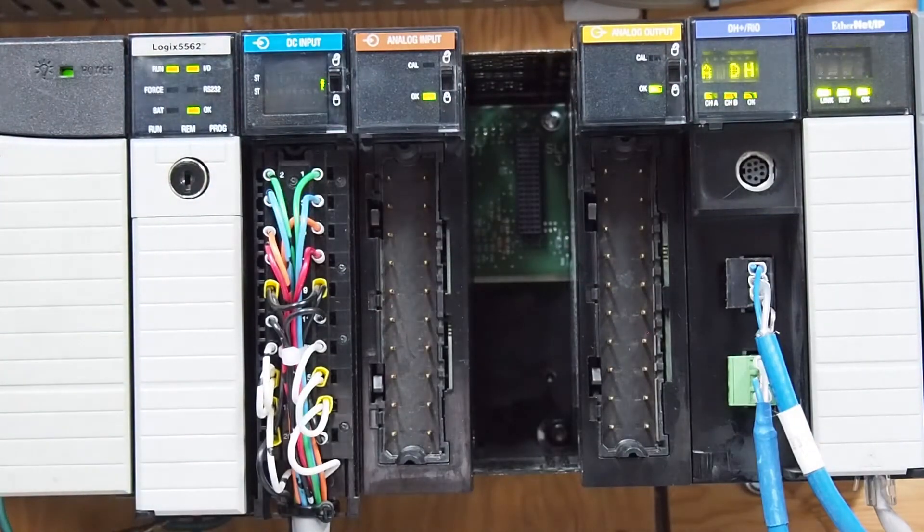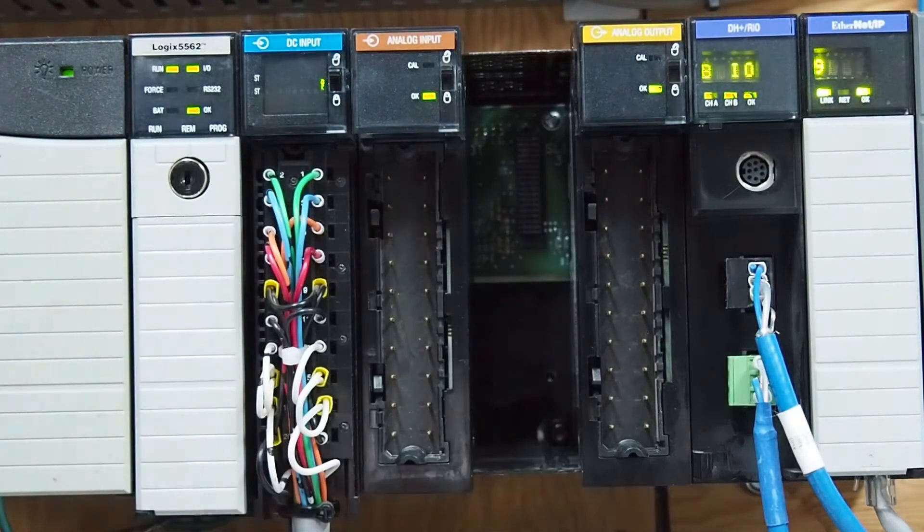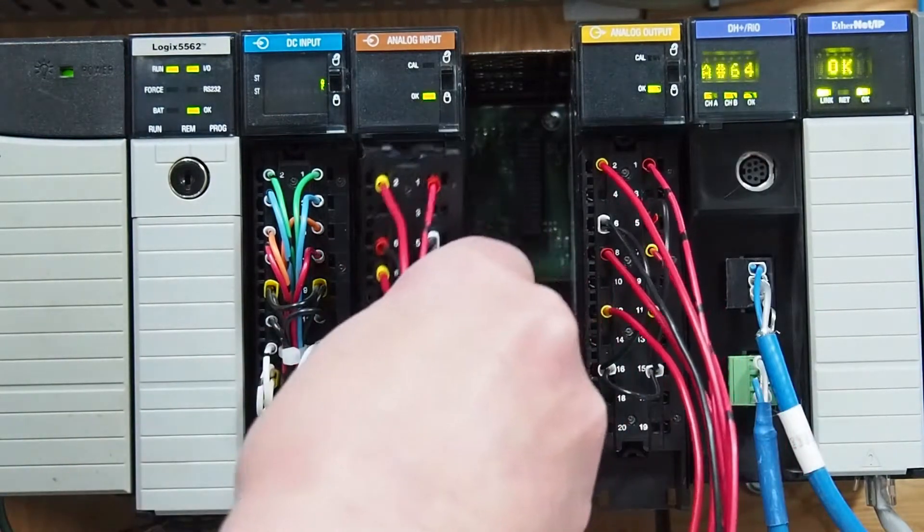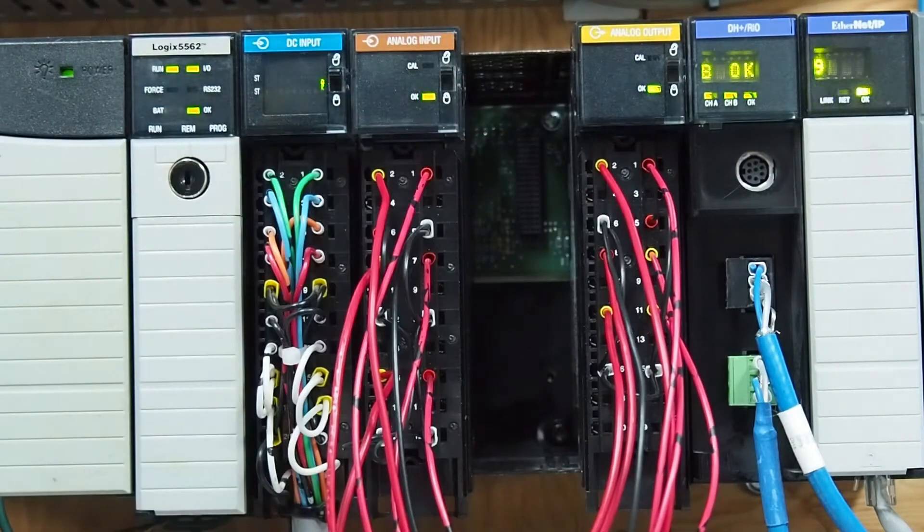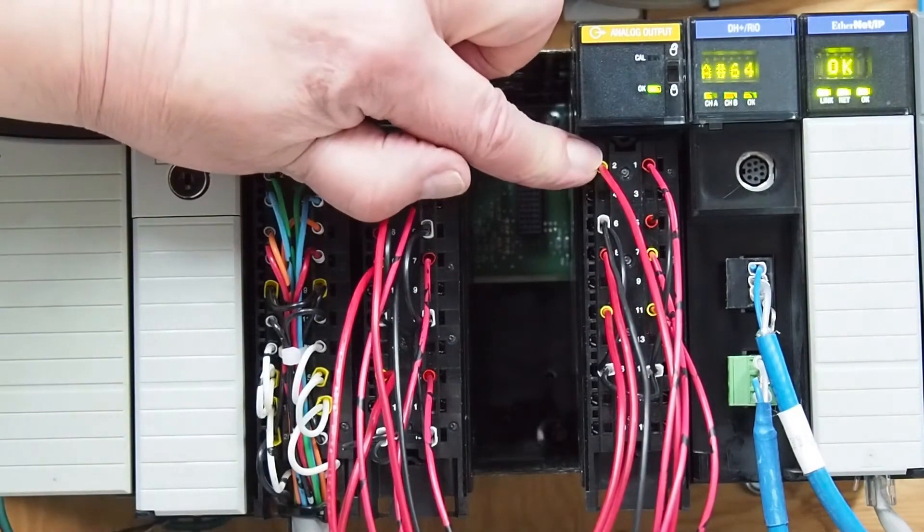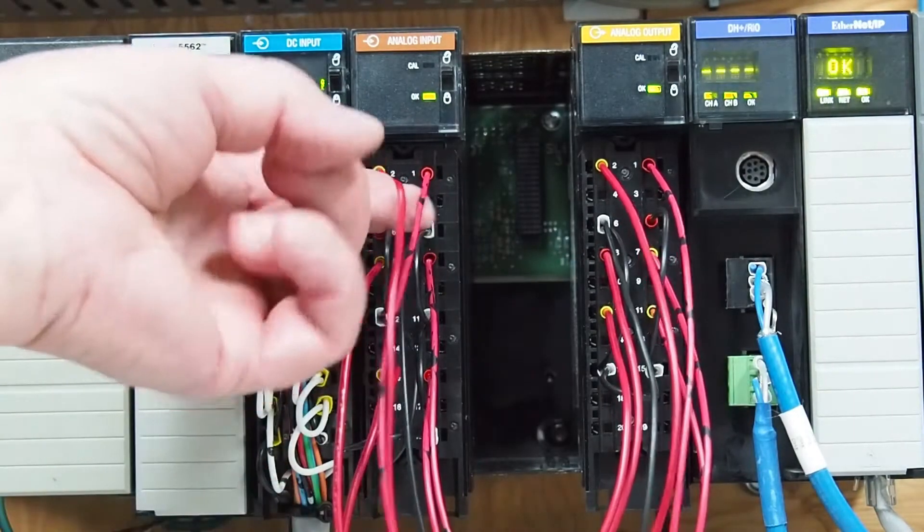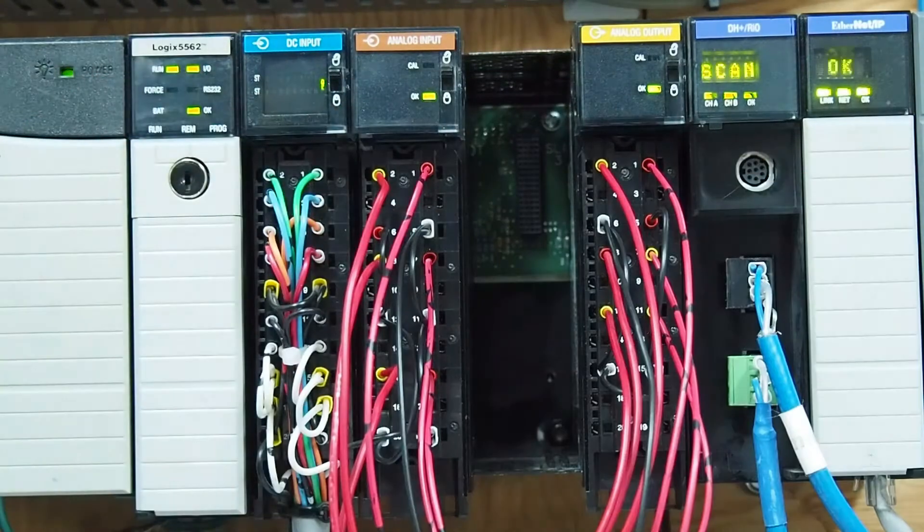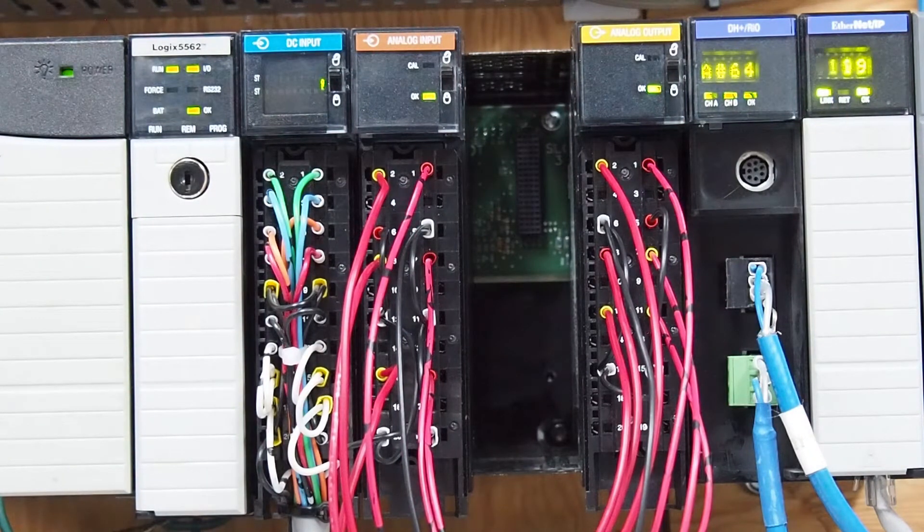If we look at the voltage wiring, it's slightly different. So here's our voltage out. And you can see on the OF8, for voltage out, it's a first terminal. For current out, it's a second terminal. And for voltage, again, you've got the first terminal. And on the current, you're using both of them. So that's the differences between the two, how you wire them up.